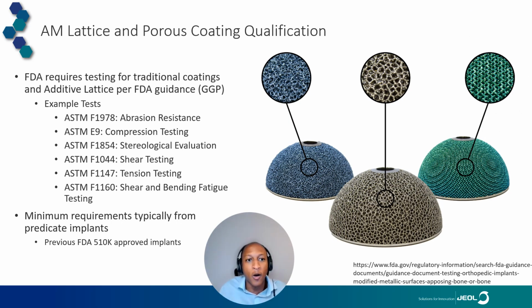In terms of utilizing lattice in an orthopedic implant, it isn't just a matter of selecting the lattice and designing it, and then going from there to qualify it and utilize it in a production setting. The FDA in the US does require testing for these traditional coatings, porous coatings, and additive manufacturing lattice, and the FDA does provide some guidance, on the bottom right, for how to test these lattices. For example, it gives recommendations on abrasion testing to confirm that under abrasive environments the lattice does not lose any of its mass, compression testing, shear and tensile testing, and also some fatigue testing for the lattice.